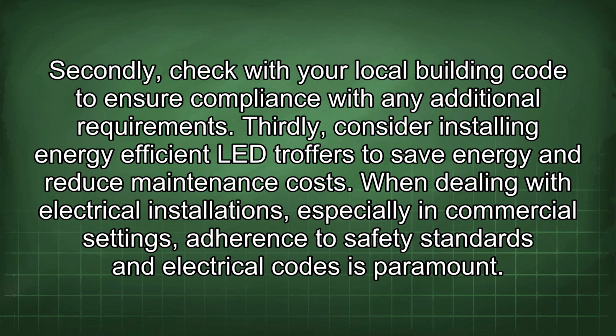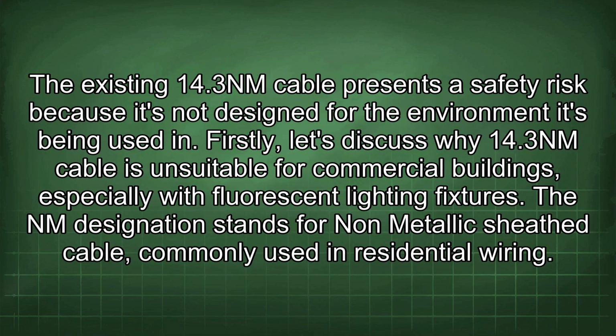When dealing with electrical installations, especially in commercial settings, adherence to safety standards and electrical codes is paramount. The existing 14.3 NM cable presents a safety risk because it's not designed for the environment it's being used in. Firstly, let's discuss why 14.3 NM cable is unsuitable for commercial buildings, especially with fluorescent lighting fixtures.